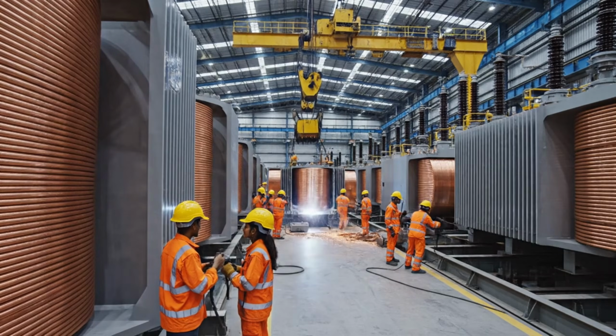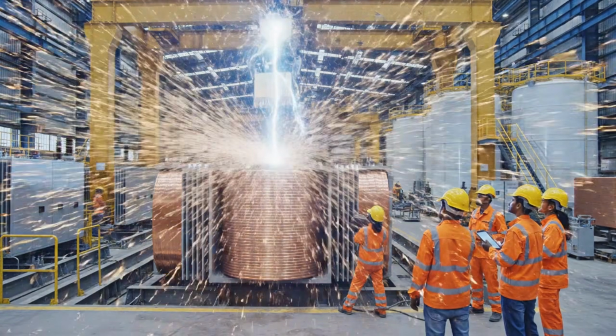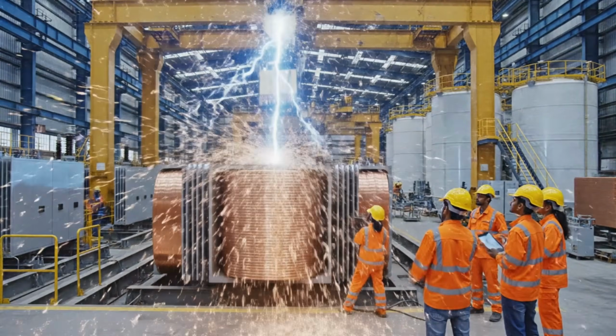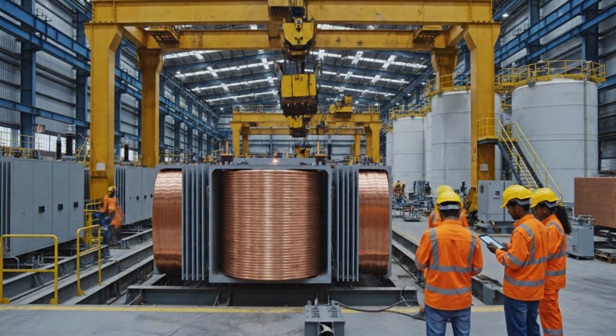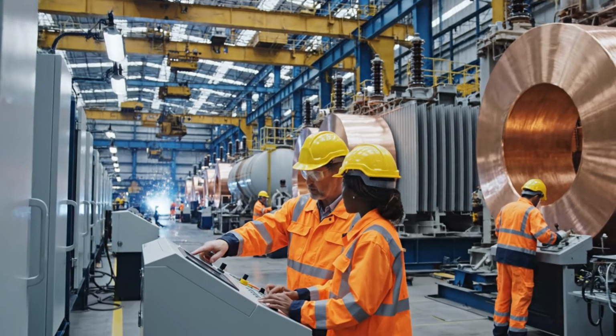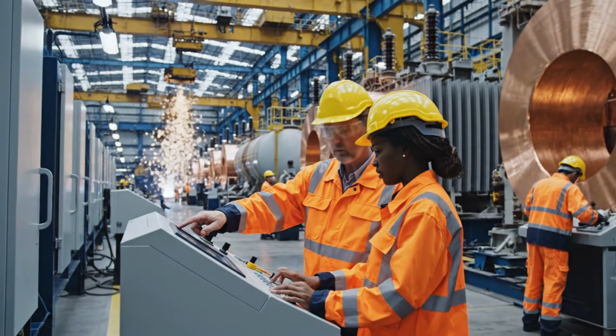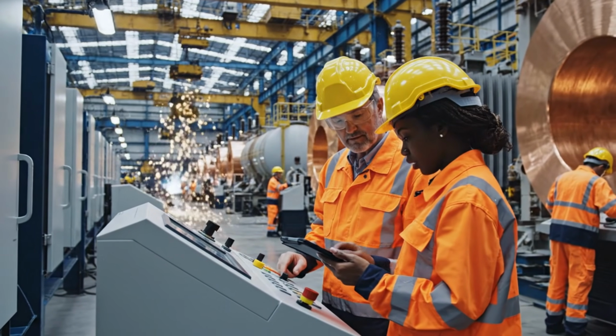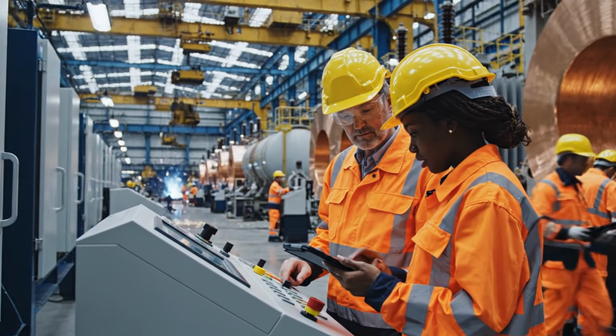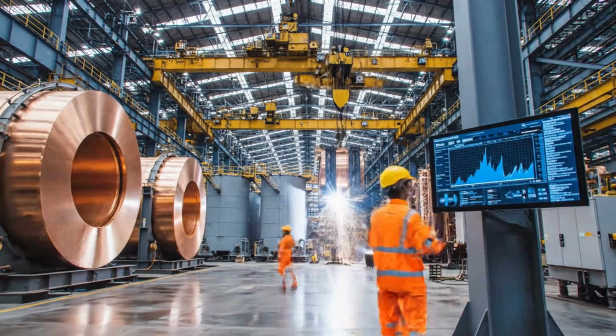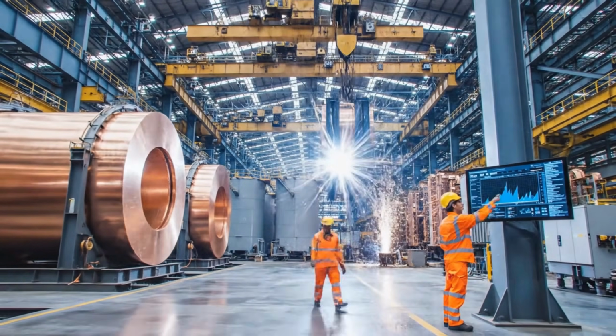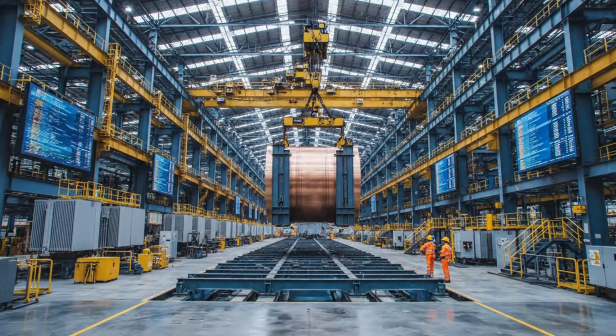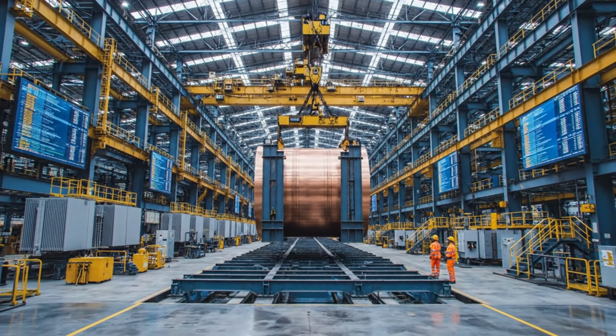Bring it down slowly, watch the clearance. Copy that, lowering now. We need to keep the voltage steady right here, otherwise the copper will overheat. Okay, I'm adjusting the current now. The readings look stable. These massive coils are the heart of the transformer, requiring precision alignment before the vacuum oil filling.